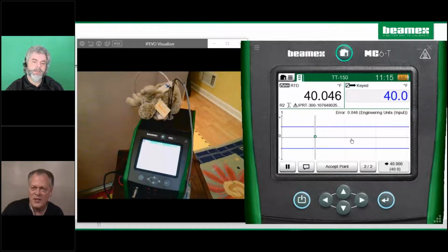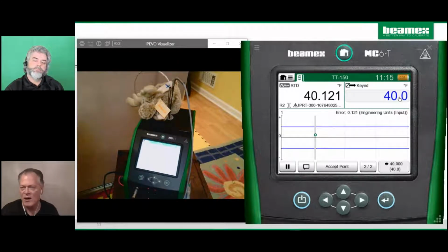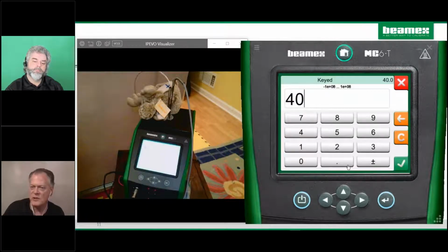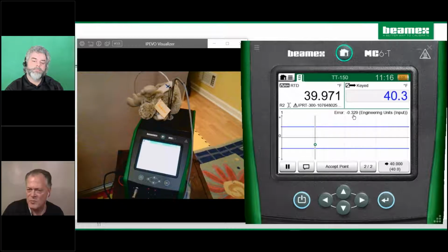Yeah, so now there is a little glitch. The dry block stopped controlling for a moment, so the temperature is running up, but it's still pretty stable. So just for expediency, I'm gonna click through here, but at this point, I would call on the radio and say, hey, control room, what do you guys see? And the guy tells me, oh, it's 40.3 right now. So it's off. In fact, it's off by 0.3 degrees to the low side, where it was 0.1 degrees on the high side. So I'm going to accept that. Okay. And the calibrator's not happy because we lost that control, but that's okay for this.